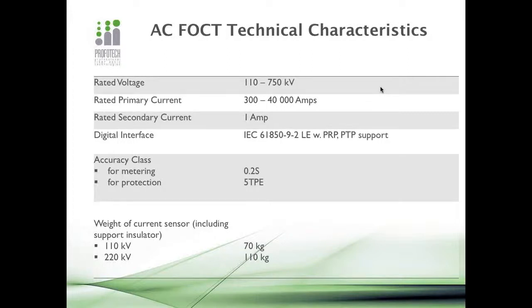Second point, what I must say, is the primary rated current. Although there is such a parameter as primary rated current, when we speak about fiber optic instrument transformers, one of the advantages is that we can use them for a range of rated currents, not for some certain 1,000 amps, but for a range between 1,000 and say 5,000 amps, and they would still be within the accuracy class. Why is it so important?